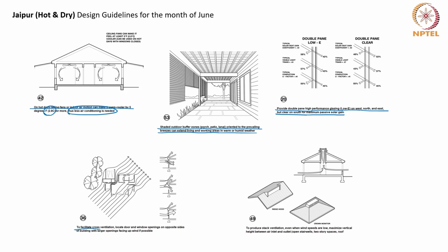To facilitate cross ventilation, we can locate door and window openings on opposite sides of buildings with large openings facing upwinds if possible. To produce stack ventilation, even when wind speeds are low, maximize vertical height between air inlet and air outlet through open stairwells, two-story spaces and roofs in the form of attics or mezzanines.